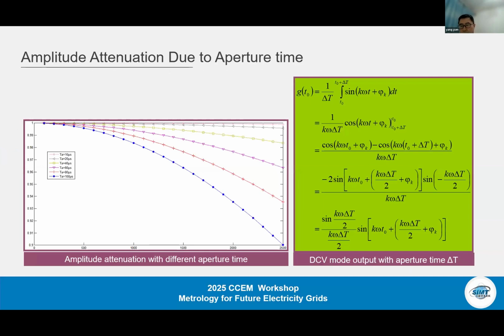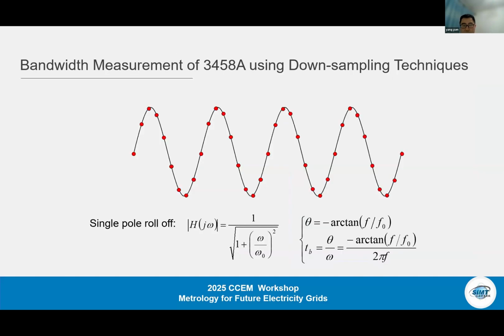Each sample is taken by integration over a time interval. The DMM effectively averages the input signal during the aperture time. Amplitude error as well as phase error can be introduced during the integration of a sinusoidal signal. This is compensated during the signal processing. One problem is that the DC input path, whether through an amplifier, an additional resistive divider, or directly to its ADC, exhibits single pole roll-off, which is normally -3 dB down at the bandwidth point. This finally influences the amplitude and absolute phase.